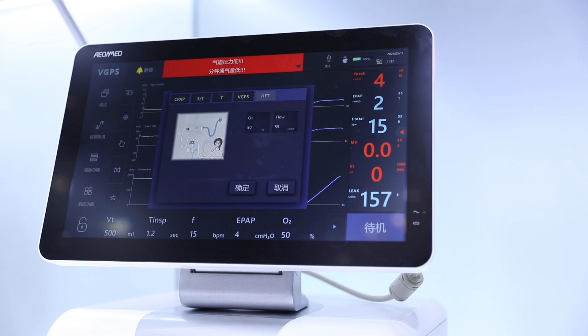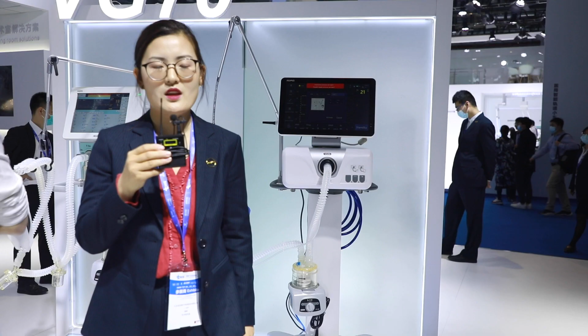CPAP with C relief options offers 2 levels of flow-based expiratory pressure relief, which improve patient comfort and the treatment acceptance. And also, VG55 equipped with high flow therapy. The flow can be adjusted from 2 to 60 liters per minute, improve gas exchange, and reduce work of breathing. SpO2 and pulse rate monitoring is also available in VG55, which gives our doctors more reference for clinical decision. And that's a very brief introduction for VG55.